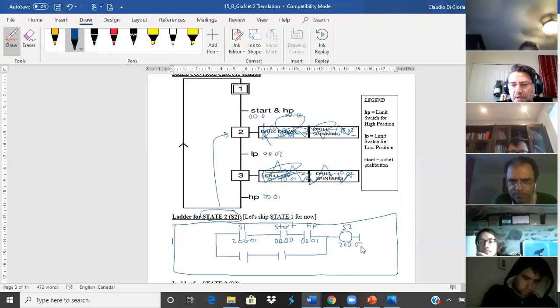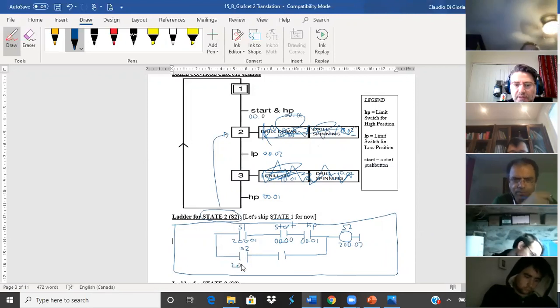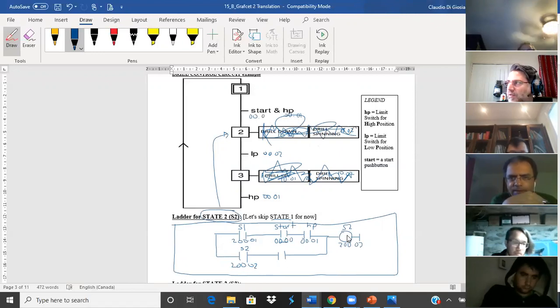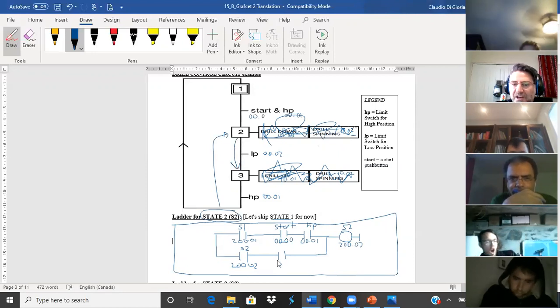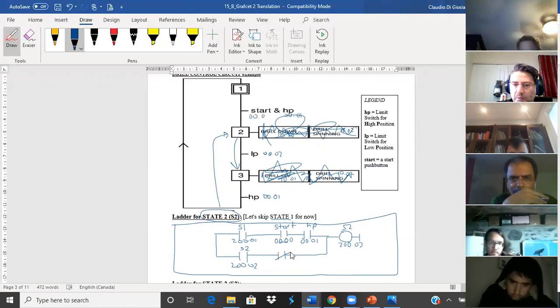How do I maintain? I maintain with itself. What does that mean? I'm on state two, I maintain state two with state two — state two being the internal bit, work bit 200.02. And how do I deactivate a state with the next state? The next state after two is three, but it's got to be normally closed, like an interlock.